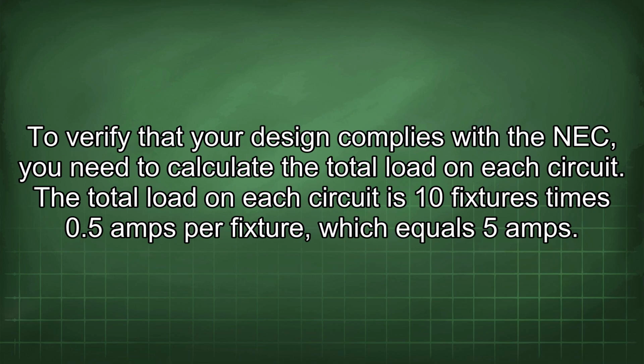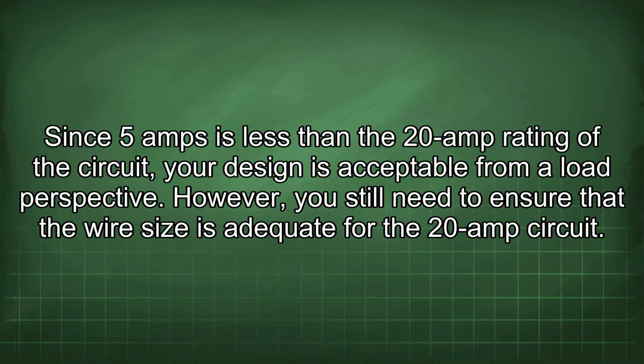To verify that your design complies with the NEC, you need to calculate the total load on each circuit. The total load on each circuit is 10 fixtures times 0.5 amps per fixture, which equals 5 amps. Since 5 amps is less than the 20 amp rating of the circuit, your design is acceptable from a load perspective. However, you still need to ensure that the wire size is adequate for the 20 amp circuit.